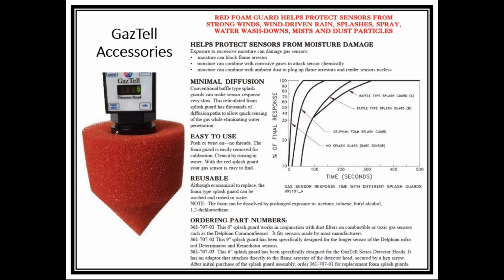The other thing that you should be aware of, I don't know if you can see by the chart, by the way, all this information that you see here is available on a data sheet, available on the rep website as well. But one of the things unique to Delphian is that you can see our foam splash guard, here's the curve with no guard at all. Of course, that's your best scenario, and if you can live with that, that's your best way of detecting gas in the most expedient way.